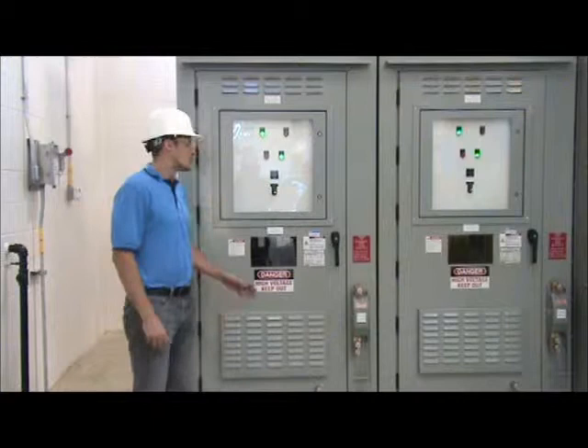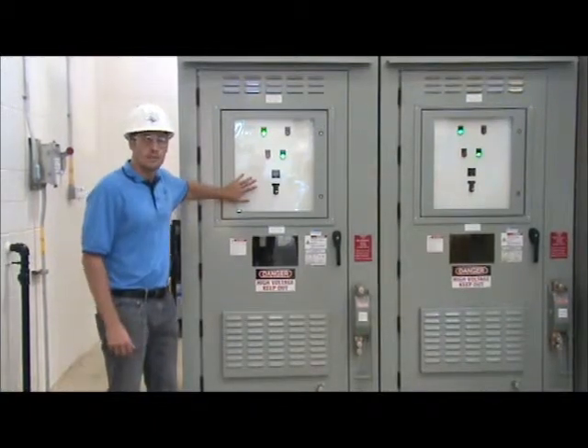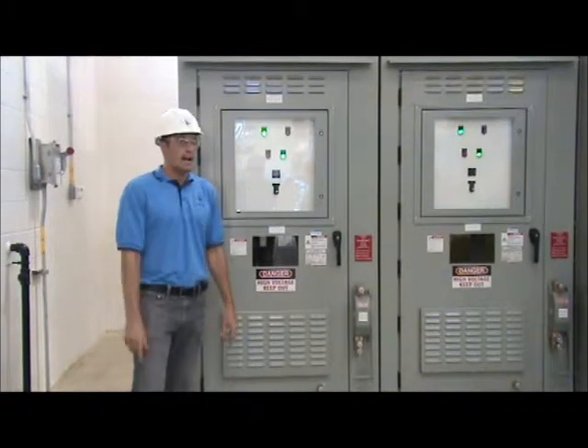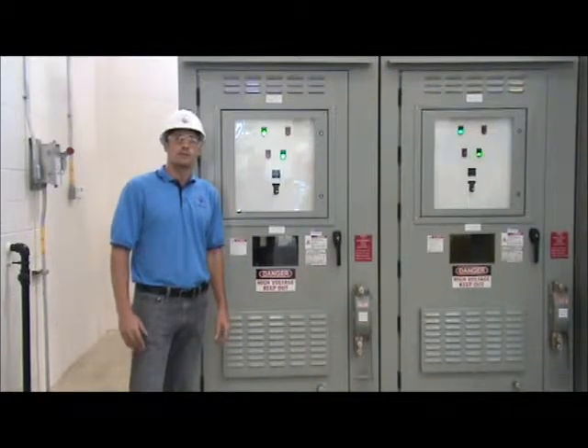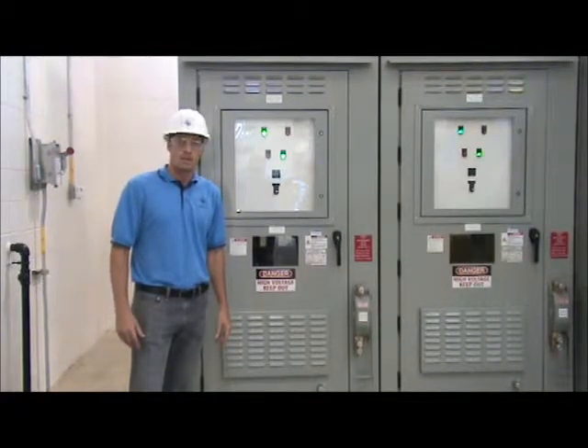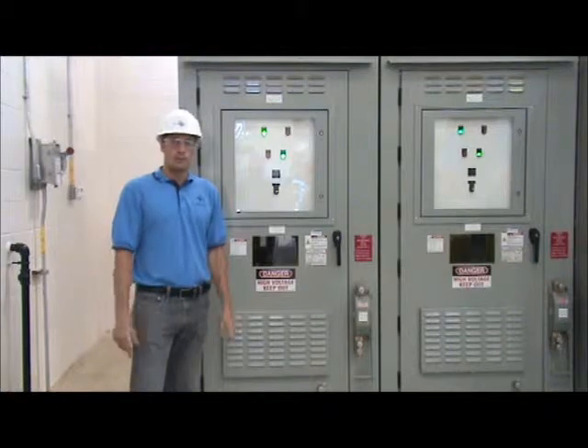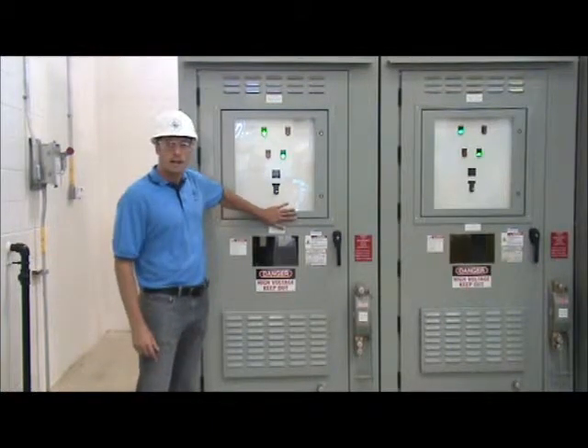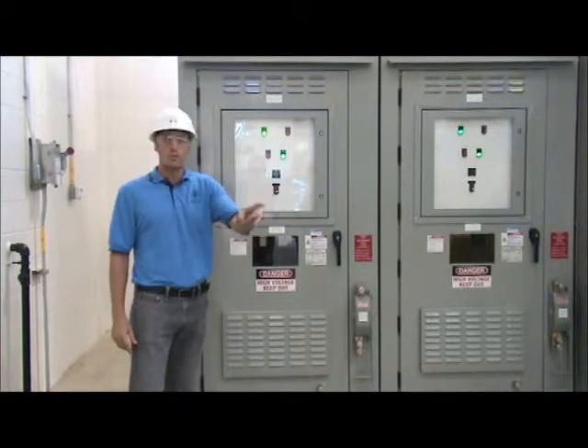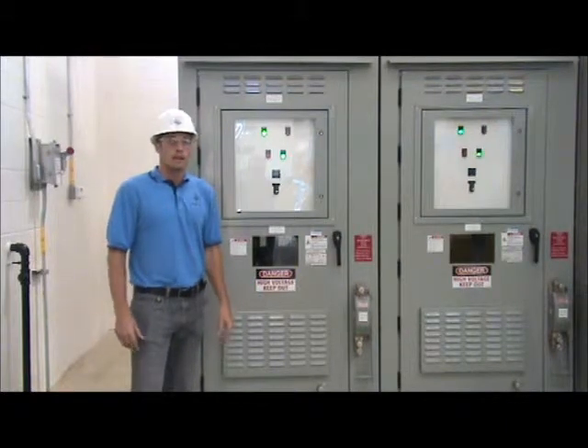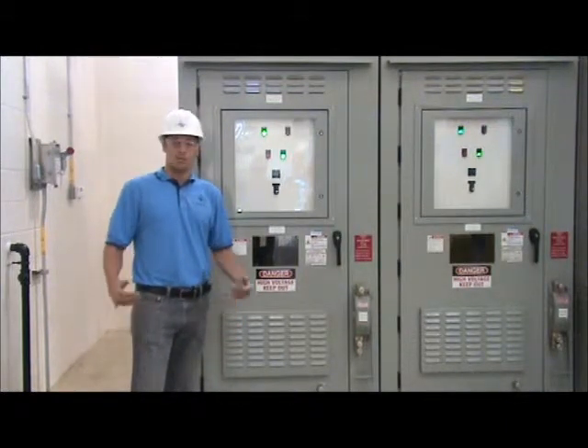Our pump controllers enable these individual capacitor banks. The controllers activate them about 4 minutes after the start of each pump. There's also an interlock that prevents closing of the cap bank while one of the individual units is starting. And then that interlock is disabled at full voltage.